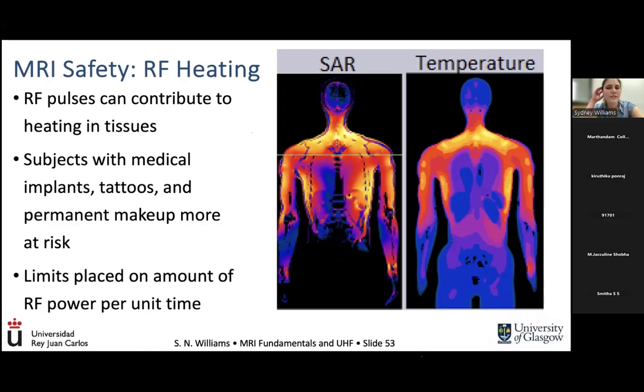And we monitor that in MRI through something called the specific absorption rate. That's related to the electric field component of the electromagnetic field, and the specific absorption rate is directly linked to temperature rise in the body. Tissue itself will absorb and be affected by radio frequency in a certain manner, but other things inside the body might be more conductive. For example, an implant, even if it's non-ferromagnetic, can be more conductive and more susceptible to RF heating. People are also commonly aware of tattoos being an issue with MRI, and nowadays permanent makeup can be of concern.